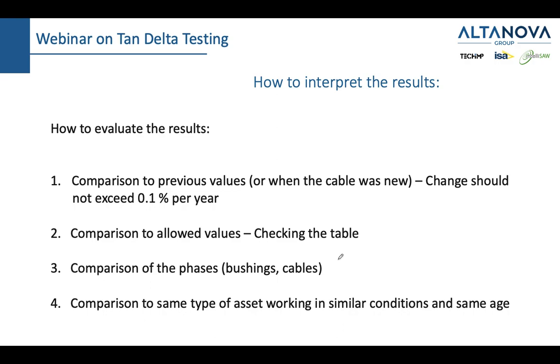And then, of course, if you cannot do any of these steps, sometimes you will have the same type of transformer. Let's say you will have a substation and two or three transformers from the same producer, same type, installed, same age, and then you will measure one and then the other, and you can compare the values between them. So this is also one way to check if your results are good.